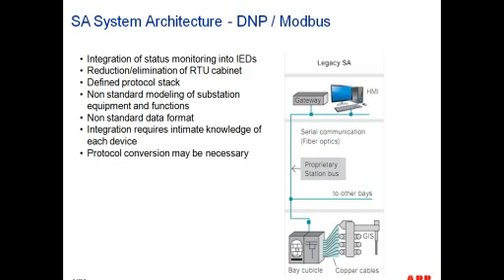Now we move on to a more current substation automation system architecture based on either DNP or Modbus, where, due to advancements in microprocessor relays and the enhanced capability that these devices started to have in the middle of the 1990s, we would use all the connections that we were bringing from the switchyard over to the relays in the form of status of breakers, trip coils, close coils, currents, and voltages. All that information was already brought onto the relays in the form of copper wires so that those protection relays could perform their protection functions. And then the idea was, why don't we add the capability so that the relays can send that information over to our remote terminal unit or substation gateway, as shown in this particular slide? And that's actually what we ended up with.